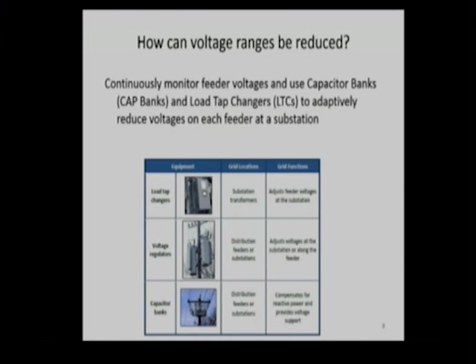I'm going to now walk through the steps to construct a new adaptive CVR system. And I'll just go through these briefly, and then I'll come back and show you some diagrams and how all of this works. First, you need to levelize the voltage along the length of each feeder. Typically, a feeder will have low spots. When the feeder gets long, out on the end of the feeder, you may see it dropping down into the low voltage level, 114 volts or so. So we need to levelize those voltages along the length of that feeder first.